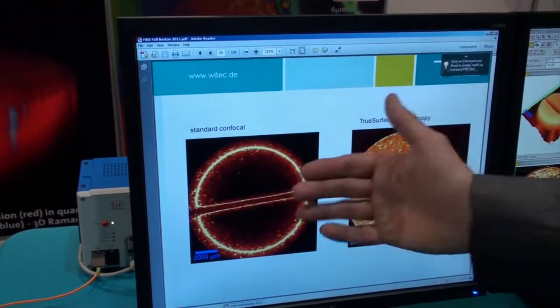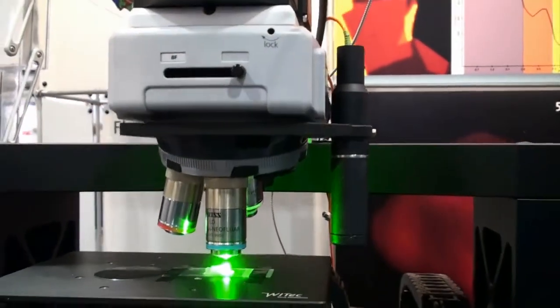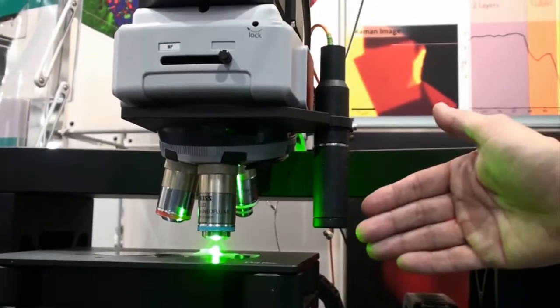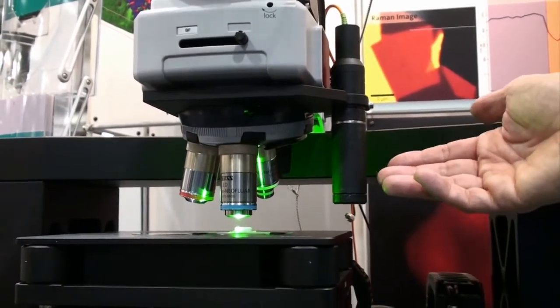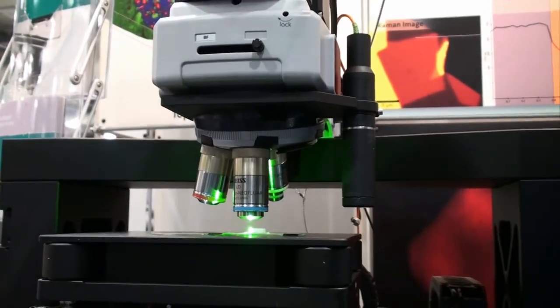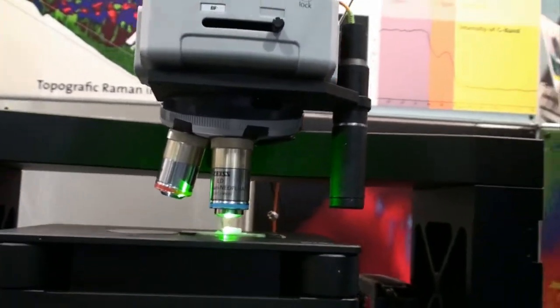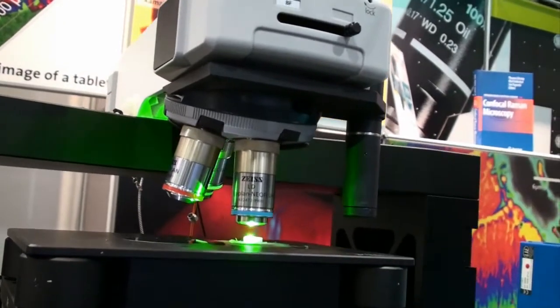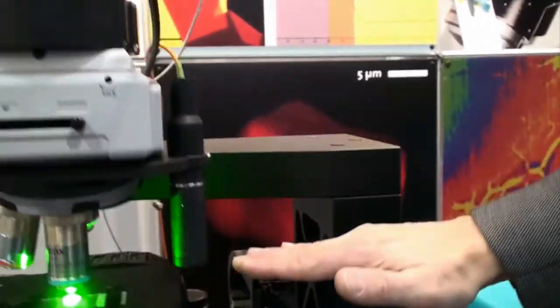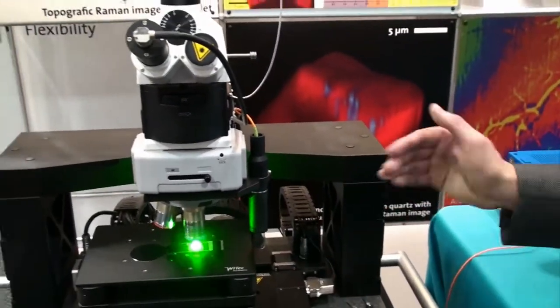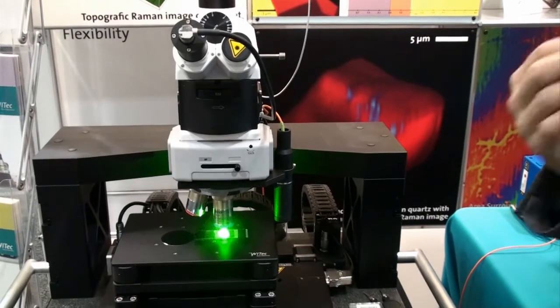With our True Surface sensor we can compensate for this. It uses a white light LED which is focused with a lens system onto the sample. The optics is a so-called hyperchromatic optics, which gives you a very good definition for every wavelength, but it has a different focal spot for every wavelength. The reflected light is coupled to a spectrometer via the same fiber. Since we have a different focus for every wavelength, the color which is reflected back gives you the topography information.